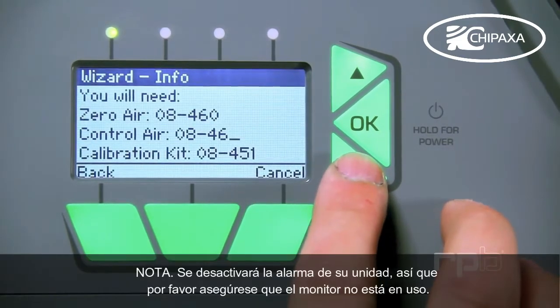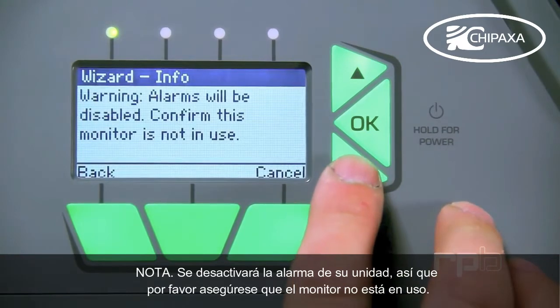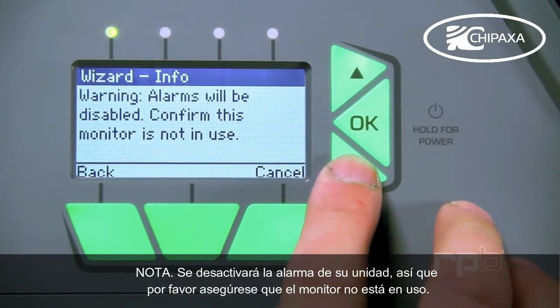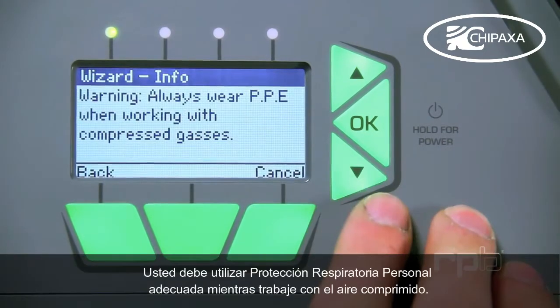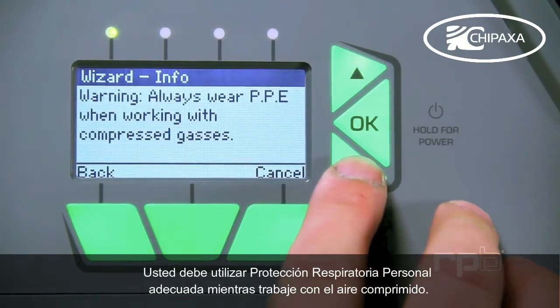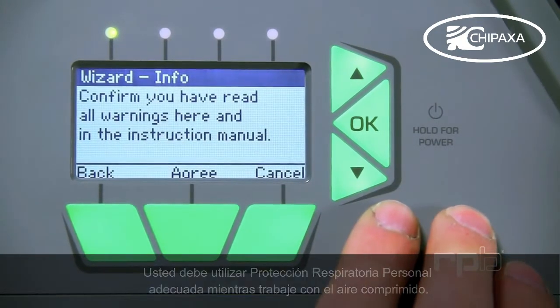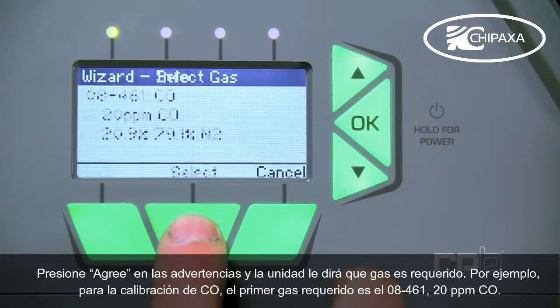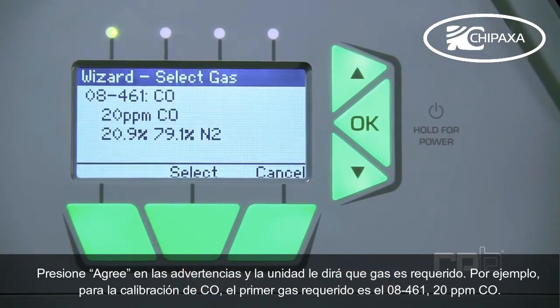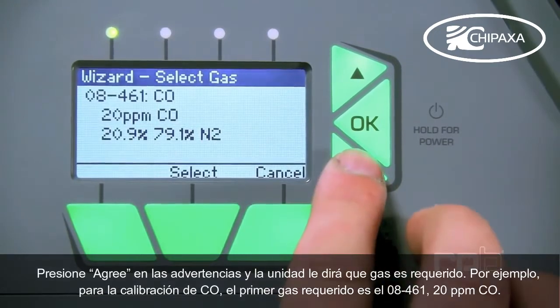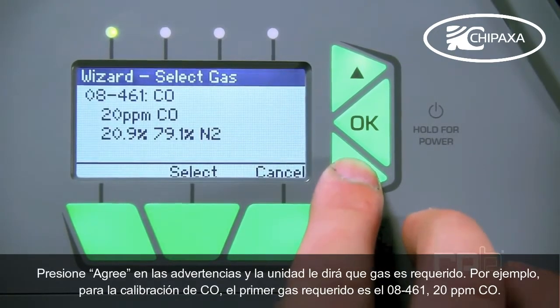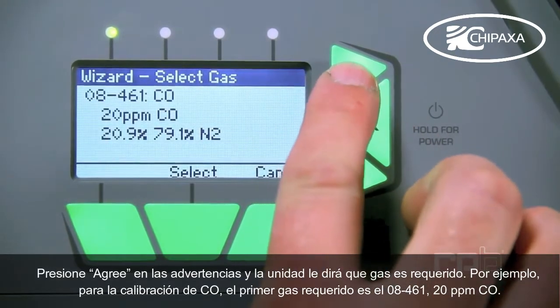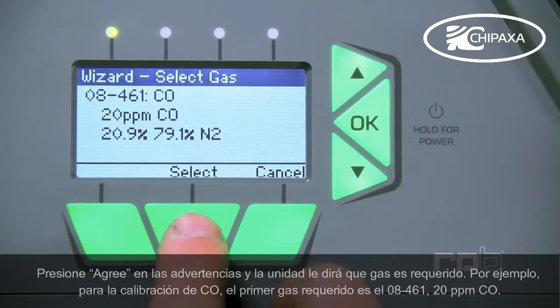Note, the alarm on your unit will be disabled, so please ensure the monitor is not in use. You must wear appropriate PPE while working with compressed air. Press Agree to the warnings, and the unit will tell you which gas is required. For example, for the CO calibration, the first gas required is 08-461, 20 ppm CO.